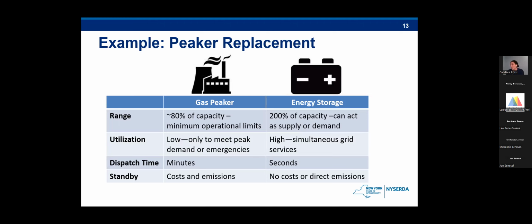They're able to provide the same service, but would not need to be on such a stringent standby requirement, as batteries can be used for other applications at the same time, while still being prepared to meet peak demand events. These older peaker plants are also paid to be on standby. So even if there's not a peak demand event, they will be paid to just be waiting for one. Energy storage also has the ability to replace these gas peakers with a much higher range of capacity. And energy storage can provide simultaneous grid services, while older peaker plants are generally slow to respond or only used for peak demand because they are expensive.